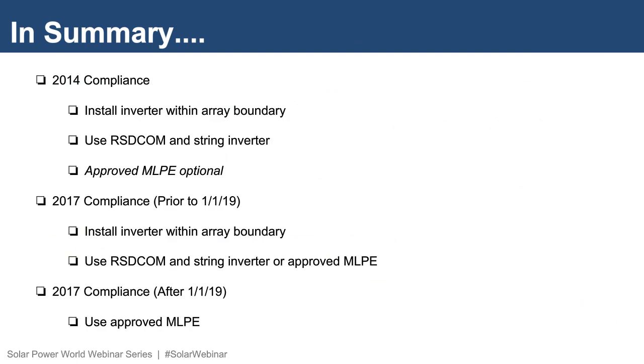In summary, I'd like to reiterate the various ways that you can comply with some design practices for rapid shutdown compliance. If your installation is in a 2014 jurisdiction, the simplest manner may be to install the inverter within the array boundary. This again allows you to meet the array level rapid shutdown and may not require any additional external combiner boxes or rapid shutdown equipment. If the inverter cannot be installed within the array boundary, we have the RSDCOM product, which can be coupled with the transformerless string inverter in order to meet the array level rapid shutdown. Finally, you may be able to use approved MLPE, such as the Tigo solution, to perform module level shutdown and in effect also meet the array level rapid shutdown.